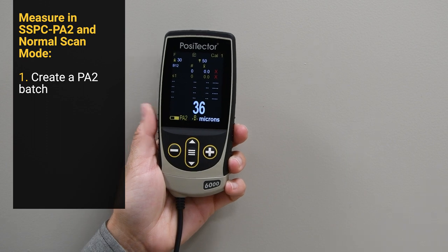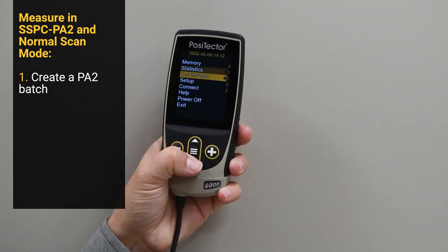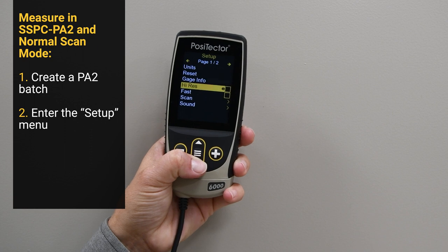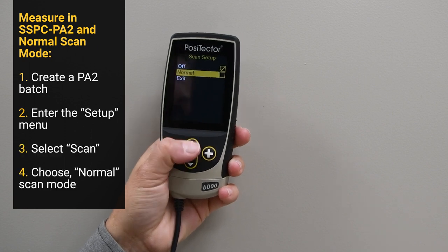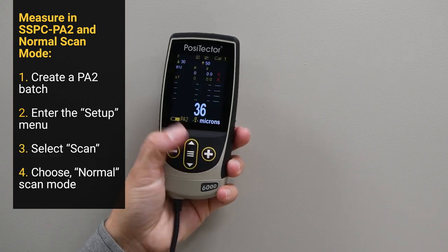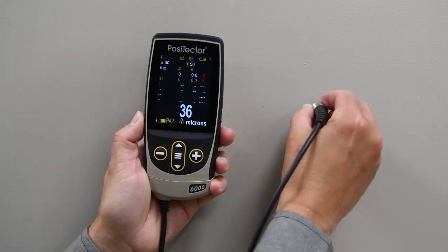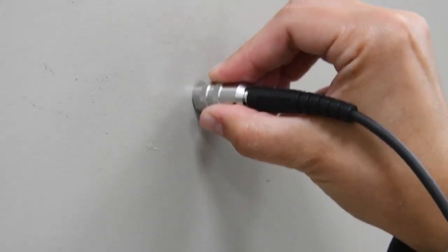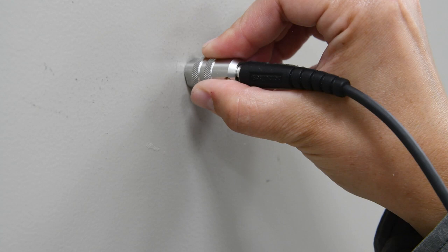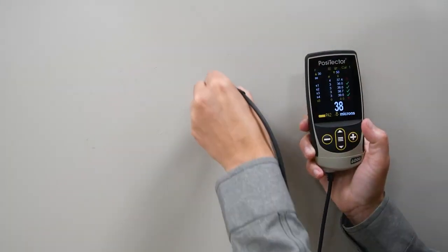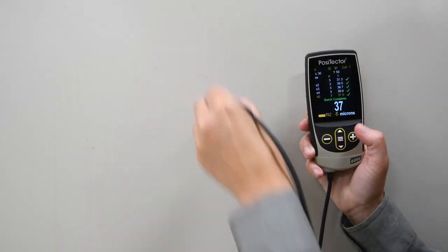After a PA2 batch has been created, enter the gauge menu and select Setup, Scan, and choose the normal scan mode. Instead of lifting the probe between each individual reading, hold the probe down and move it in a circle to quickly capture all 3 spot readings. Using PA2 mode and scan mode together, each area can be measured in seconds.